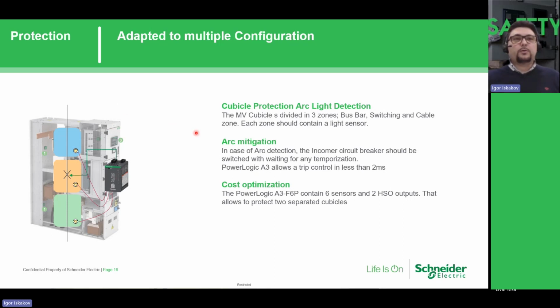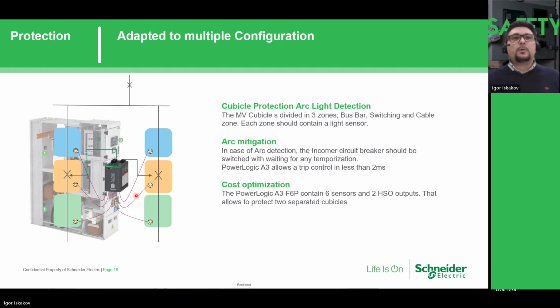But now with our new system A3, we are able to cover fully selectively 2 bays with 6 sensors, providing a trip exactly on the circuit breakers, dedicated by the trip contact with a time of 2 milliseconds with high speed outputs. We can also send a command by the internal bus, which is way faster compared to a combination of digital inputs and outputs. We can send it to the upper level unit A3, which can provide the same trip, also faster than 2 milliseconds. This can bring us very fast arc flash protection on the whole solution of this substation.